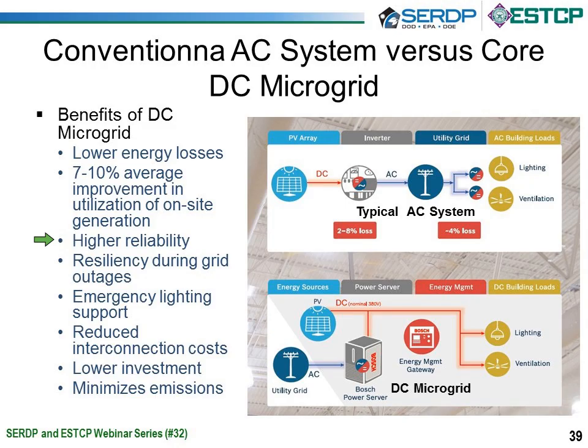And take lighting for an example, as we move toward LED lighting, the LEDs themselves have a very, very long lifetime. And it's the electronics associated with it that is now going to become the weak link. If we move to DC, that electronics is no longer the weak link and it will last as long as the lighting itself. So that's significant, especially as we talk about some of our target applications, which are high bay buildings, where there is significant cost in maintaining lights which are 30, 40 feet in the air.